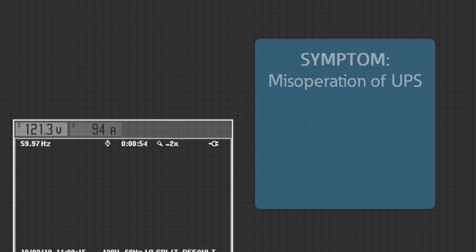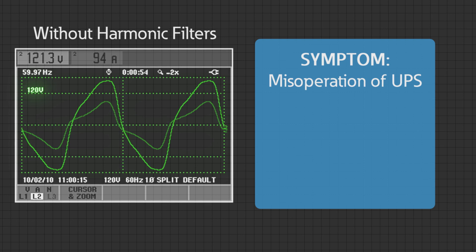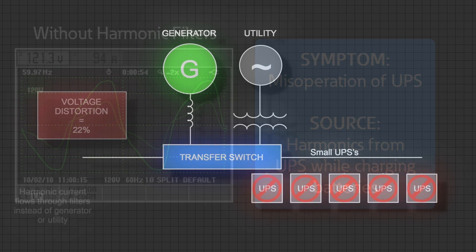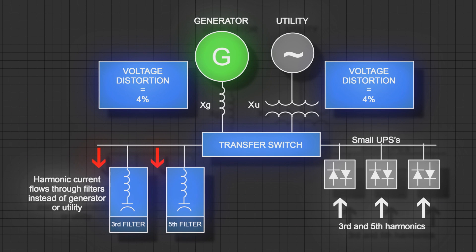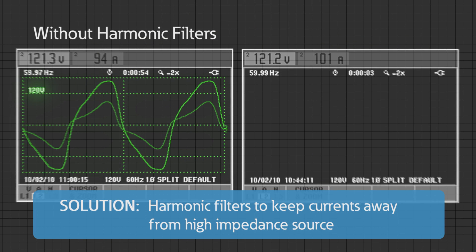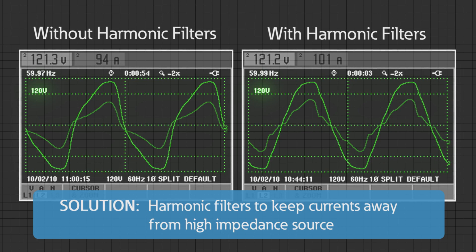So what did you figure out in that case? The symptom was the misoperation of the UPSs, and they were also the source of the harmonics interacting with the high impedance of the generator. The solution was to design and build two harmonic filters — third and fifth harmonic filters — so that the voltage distortion was limited to a similar level no matter which source the system was running on.